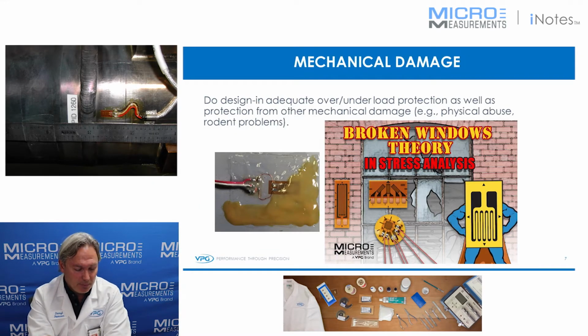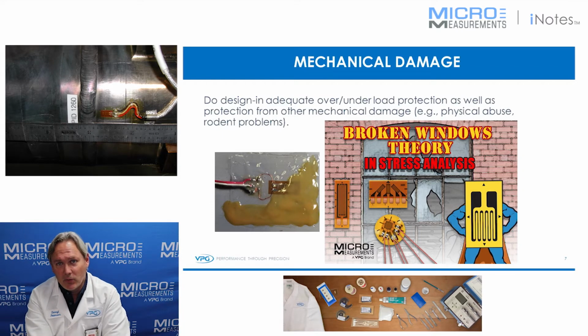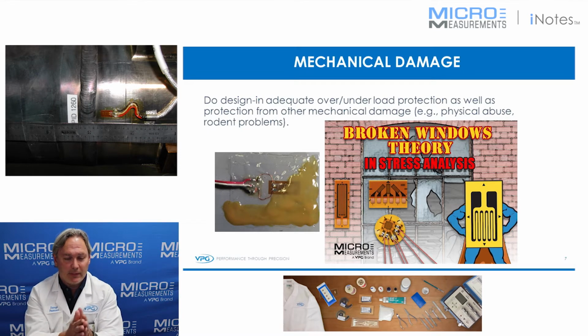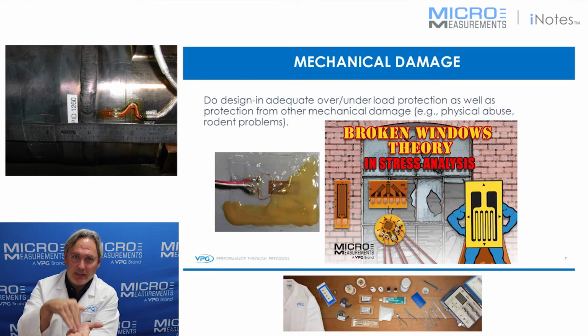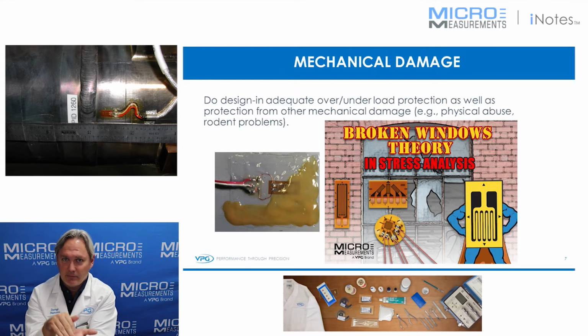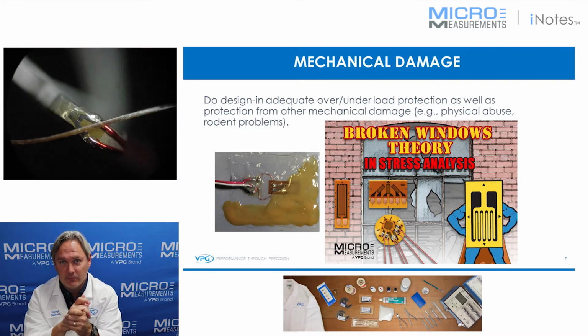Do design an adequate over and under load protection as well as protection from mechanical damage. So what we're saying here is think about what the loading levels are, and also think about whether or not the strain gauge may see some physical contact. A strain gauge cannot have something come in contact with it, otherwise you would damage it. So you need to think about that. Some customers want to think a strain gauge is sensitive to strain in the normal direction, and that's not true. It's not sensitive to strain or pressure normal to the surface. It's the in-plane strain that it's sensitive to. This is a big one.